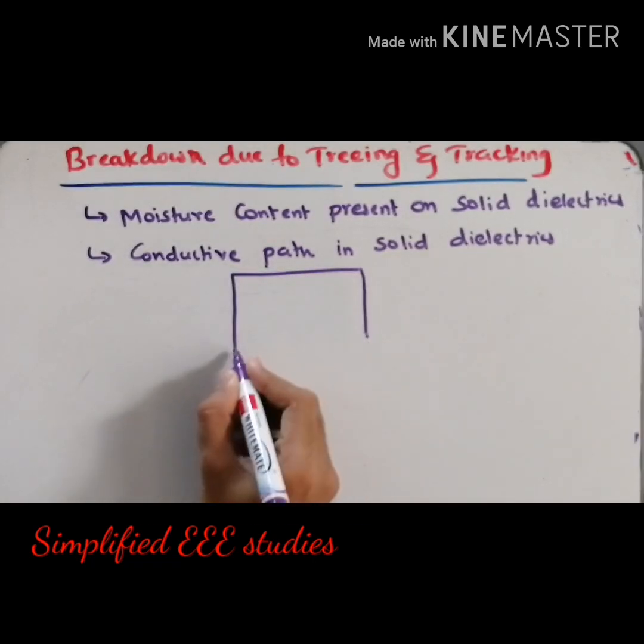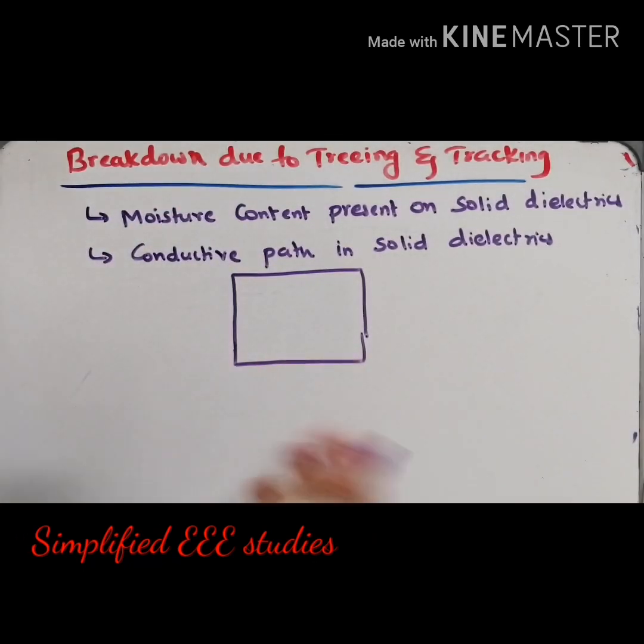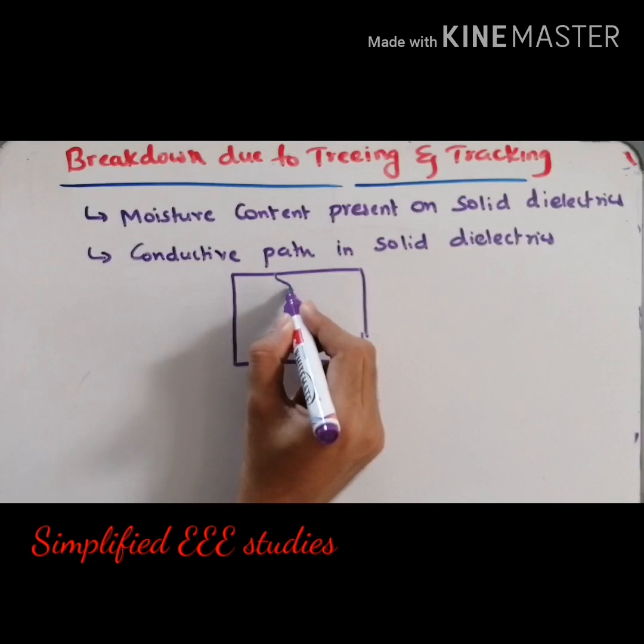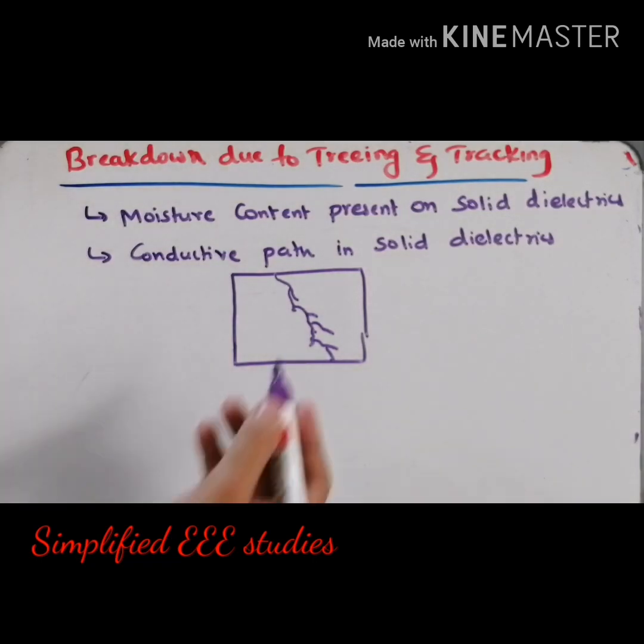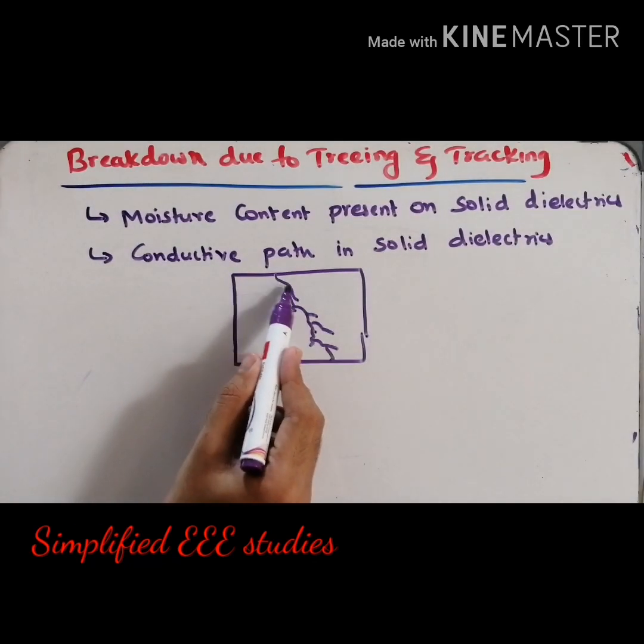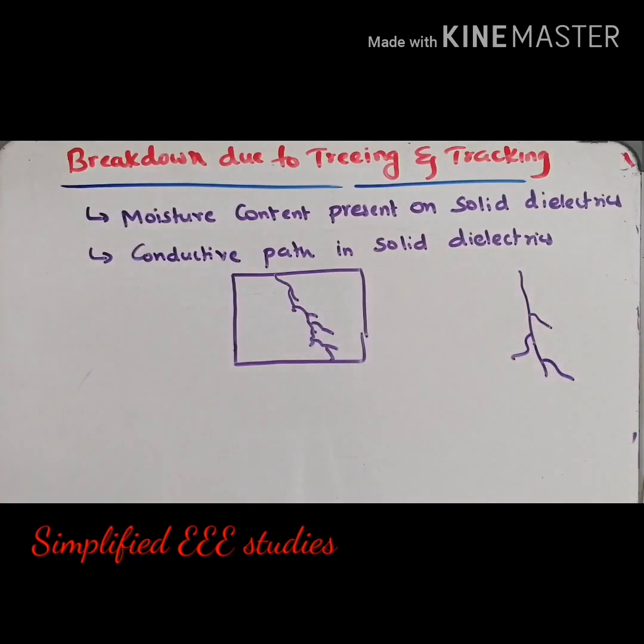Suppose this is a solid dielectric test piece. You are operating it under high voltage. Because of the moisture content over the surface, after applying high voltage for a very long duration, a small amount of conductive path will be generated inside the solid dielectric test piece. If you look at this particular path, it looks like a tree with several branches. That is why it is known as treeing and tracking — a phenomenon generally observed in solid dielectric materials.